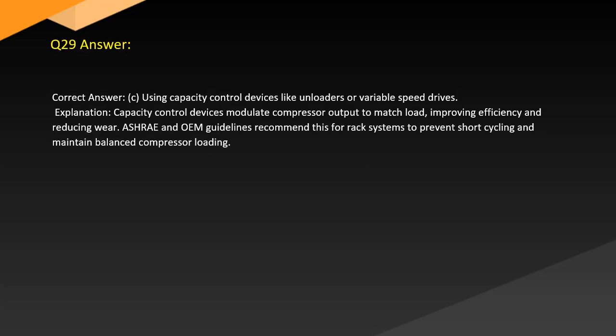Answer. Correct answer: C. Using capacity control devices like unloaders or variable speed drives. Explanation: capacity control devices modulate compressor output to match load, improving efficiency and reducing wear. ASHRAE and OEM guidelines recommend this for rack systems to prevent short cycling and maintain balanced compressor loading.